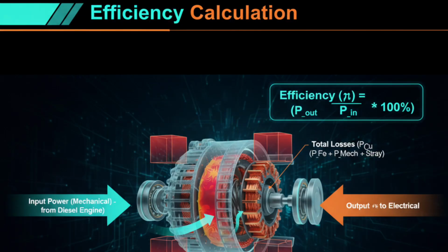Efficiency calculation. This slide shows mechanical input power coming from a diesel engine into the alternator, while electrical output flows toward switchboards and bus bars. Between them, blocks representing losses are clearly visible, along with the efficiency formula and a load versus efficiency curve. Efficiency is defined as electrical output divided by mechanical input, or alternatively output divided by output plus total losses.